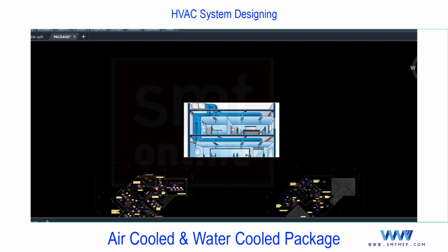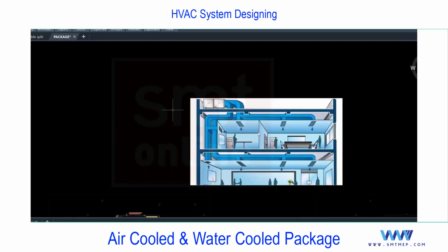I add one image also to understand the concept. You see, here this is an air cooled package. You can consider this as a supply duct, and this is return. You see, supplying the air to this, say, first floor, supplying the air to the ground. At the back side, this duct is continuing, and it is supplying the air even to this ground floor. And you see return from the ground floor is here.